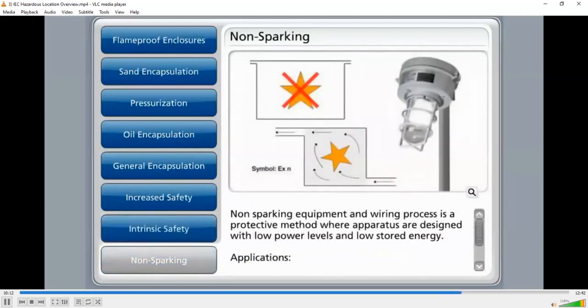Non-sparking equipment and wiring is a protective method where apparatuses are designed with low power levels and low stored energy. This ensures that an arc produced during normal functionality of the equipment or as the result of equipment failure has insufficient energy to ignite the hazardous atmosphere. The general application for non-sparking protective methods would be used for motors, lighting, junction boxes, and electrical equipment.